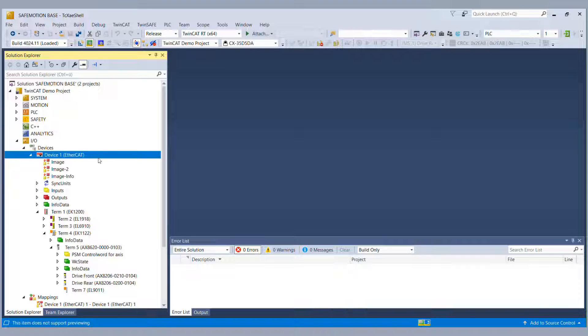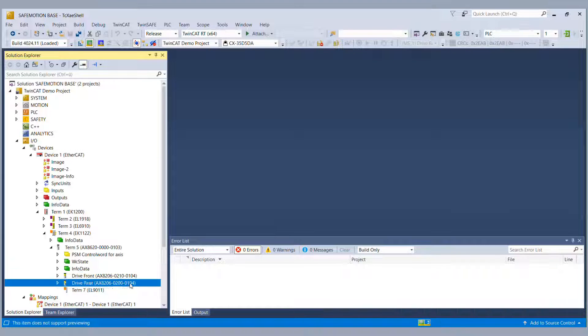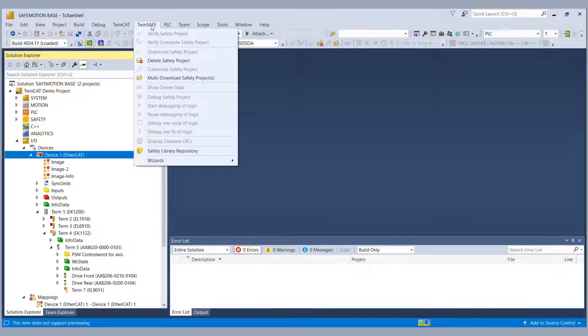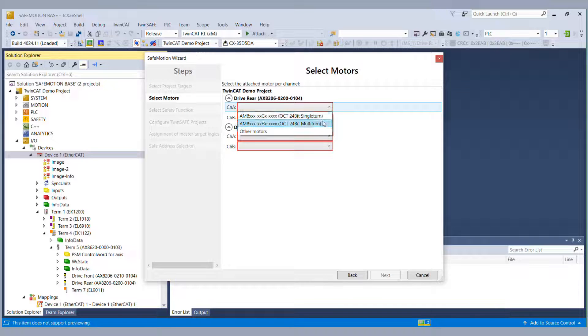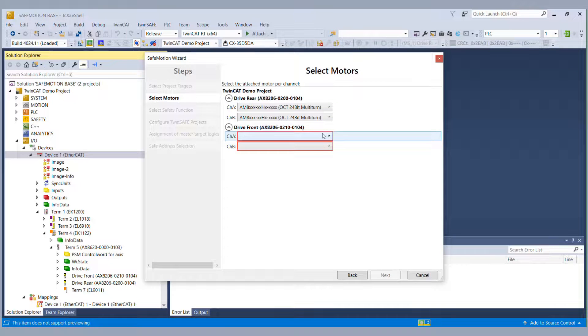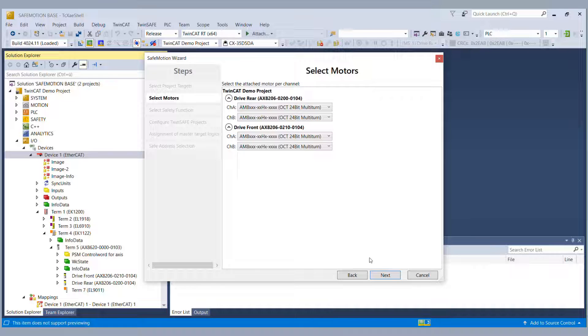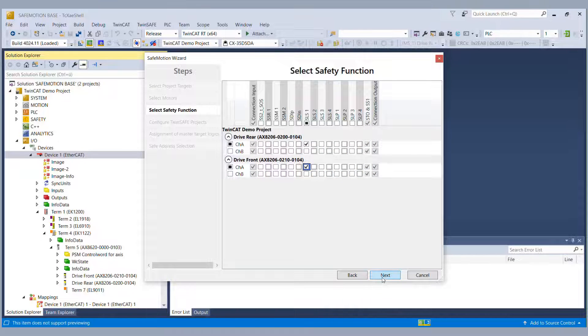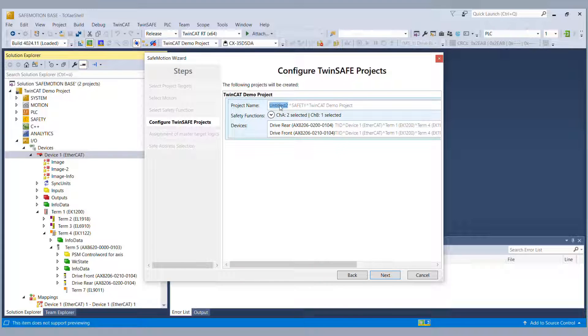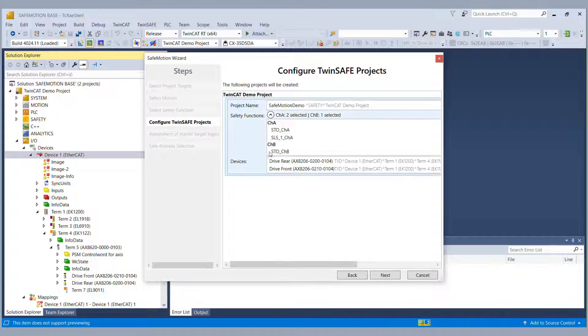As mentioned, we are starting with an existing TwinCAT 3 project with an IO configuration including our AX8000. Via the context menu — TwinSafe Wizard → Safe Motion Wizard — we can start the TwinSafe Motion Wizard. In the first step, we choose our existing AX8000. In the next step, we configure the feedback, choosing from single turn, multi turn, or other motors. If you want to use EnDat 2.2 safety, for example, you choose other motors. In the next dialog, you choose which safety functions you want to realize. In our case, we want to realize safe limited speed on channel A on the AX8000.